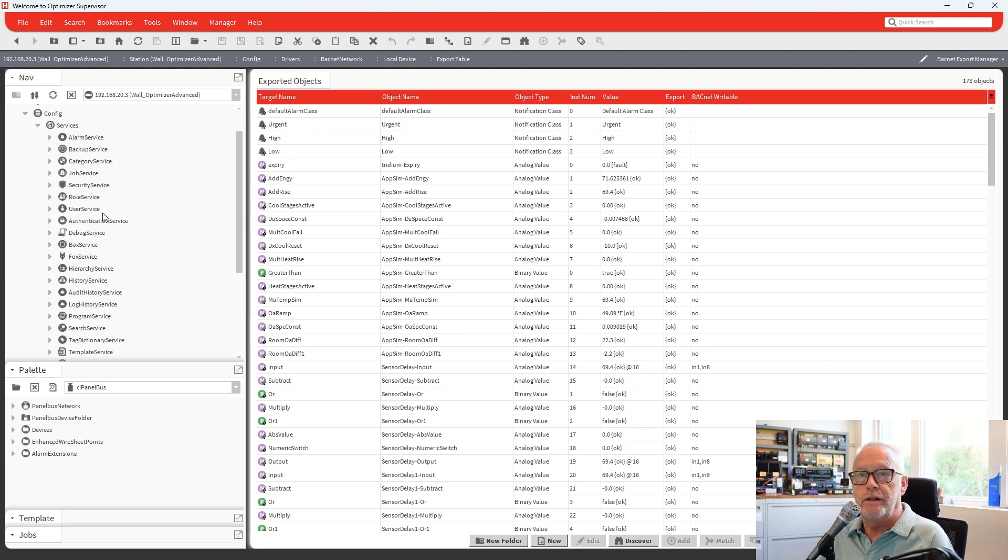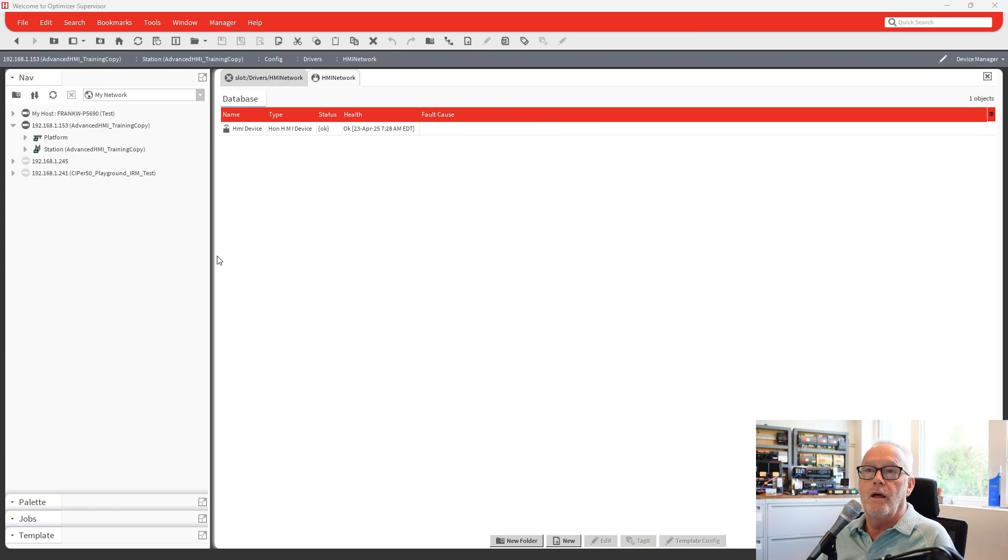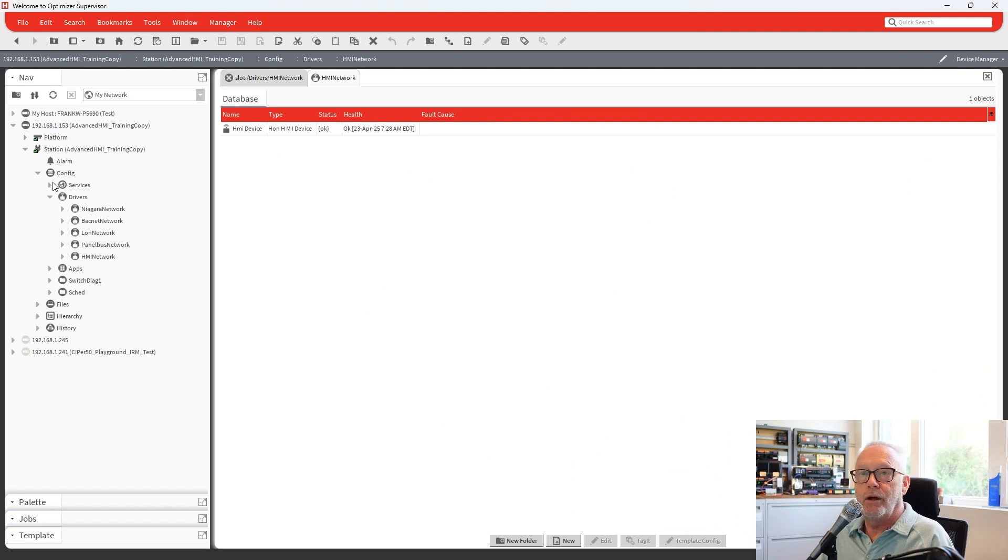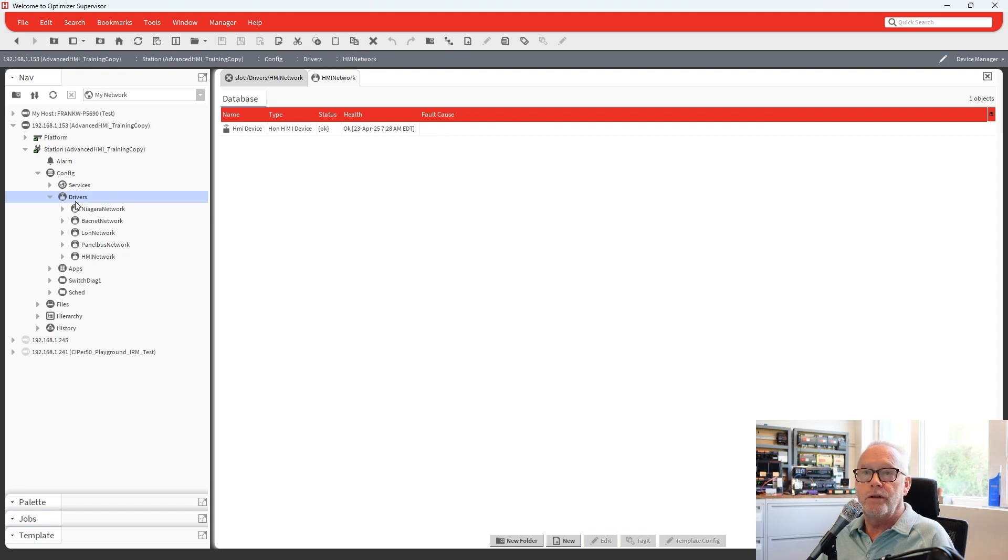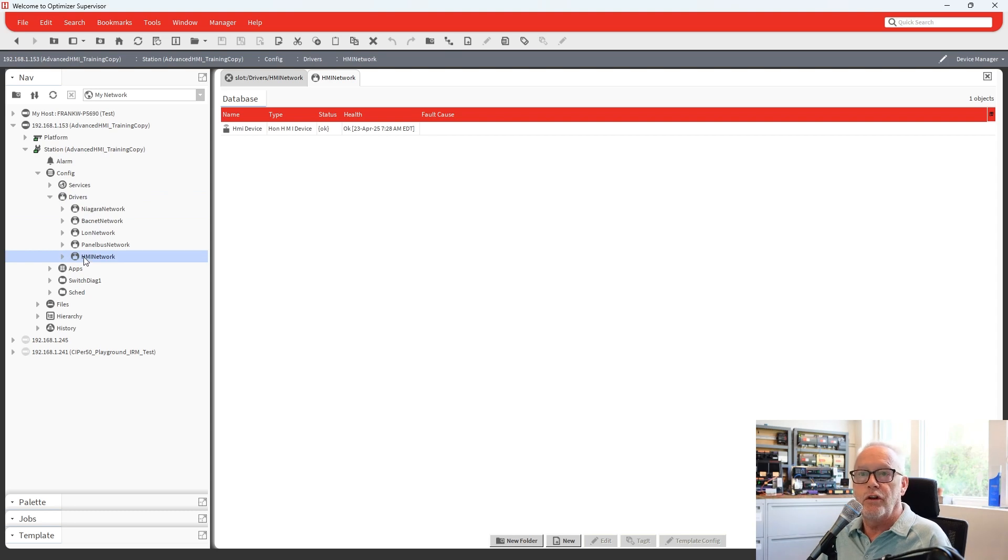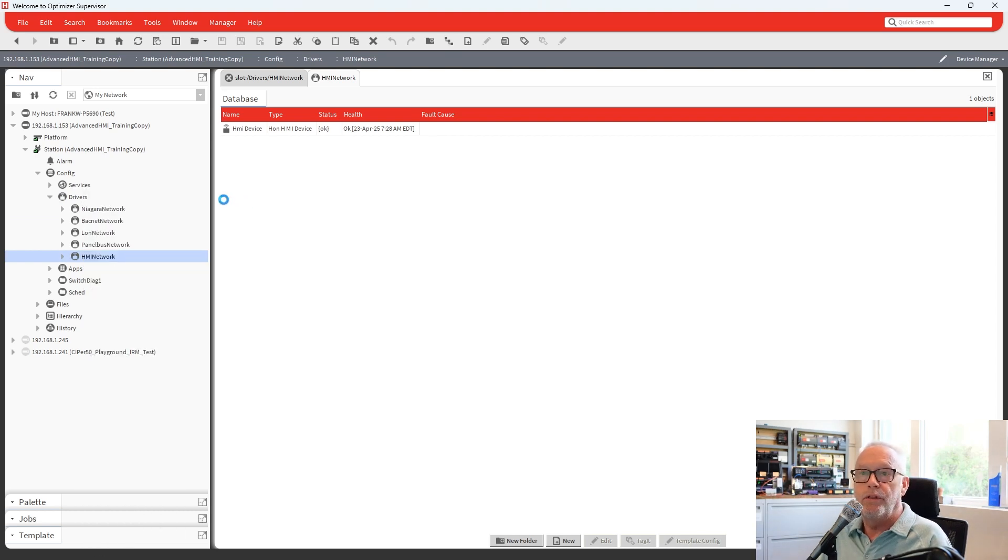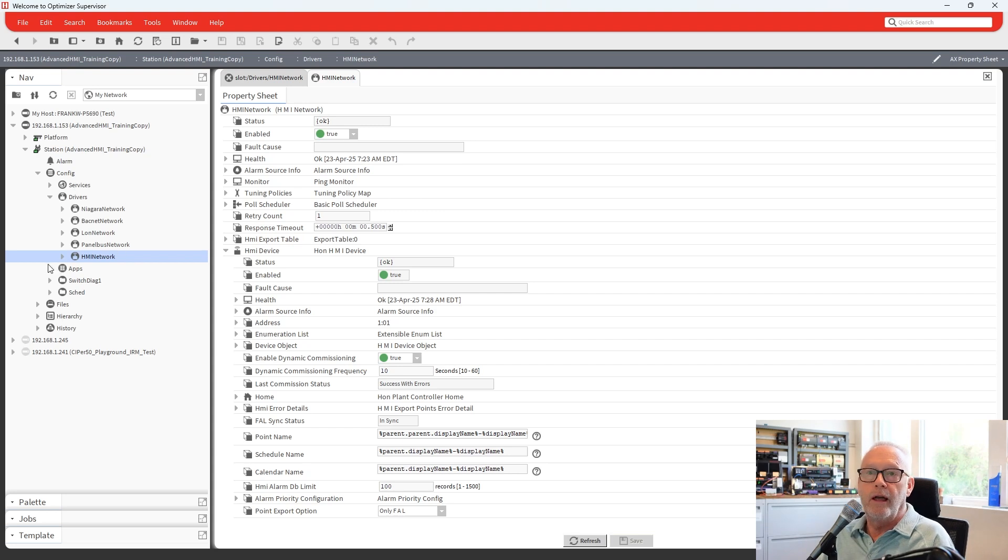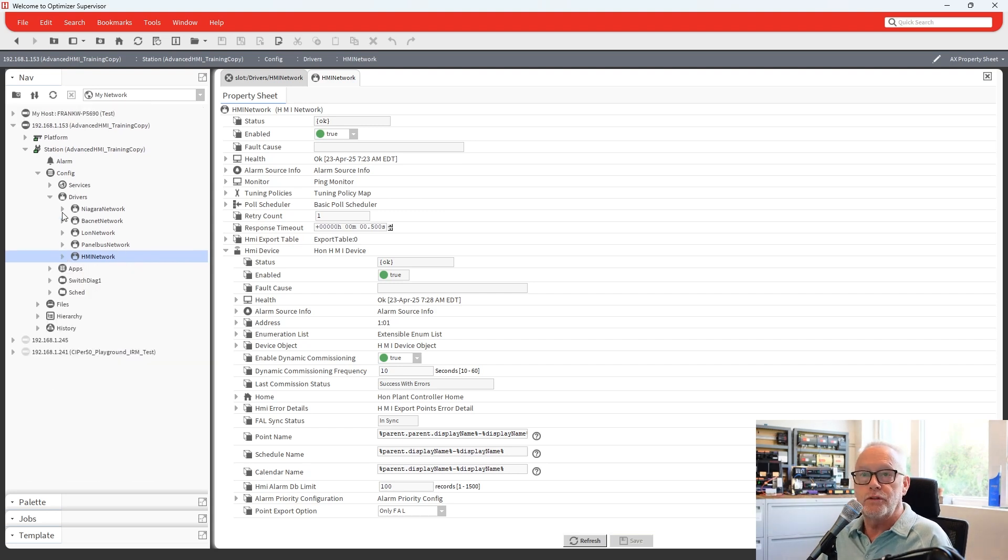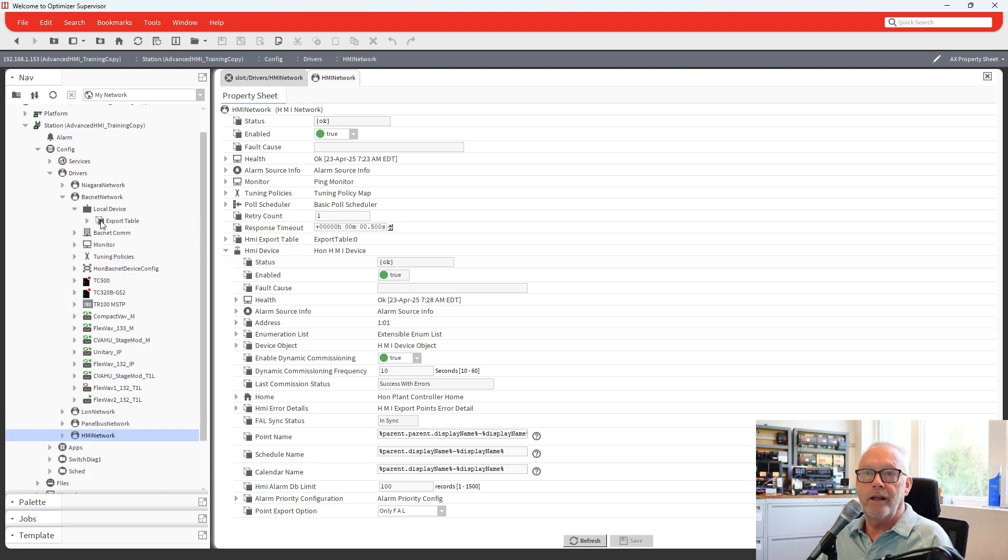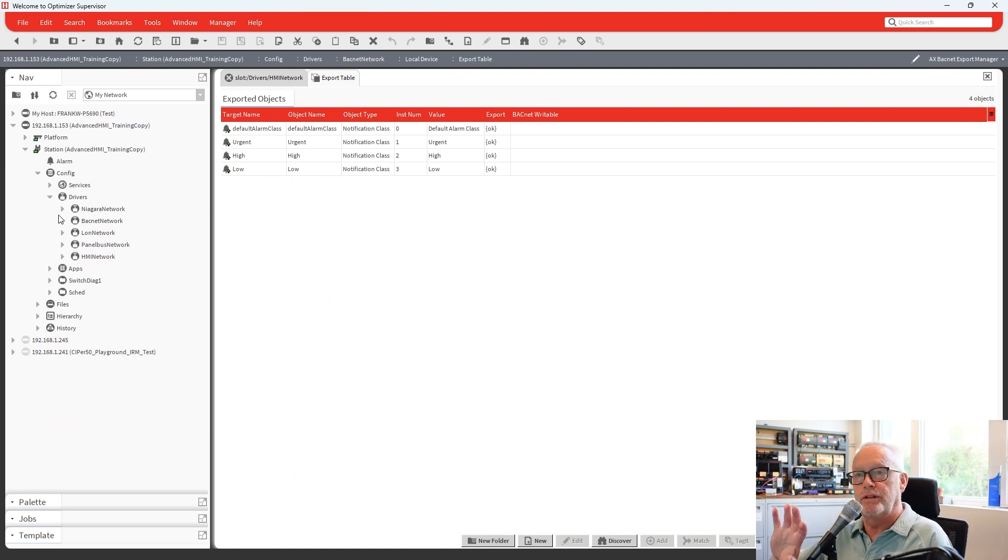And what you need to do there is, within 4.14, what they've done is they've changed how the HMI is communicating with the station and how it's set up. Now, instead of being under the BACnet network, it actually has its own dedicated HMI network. And all of its configuration is done within that area. Rather than being in the Honeywell plant controller service under services, it's now done in its own network. And it actually has its own export table that you would work with. So it's no longer part of the BACnet network export table. So it's totally separate from BACnet now.